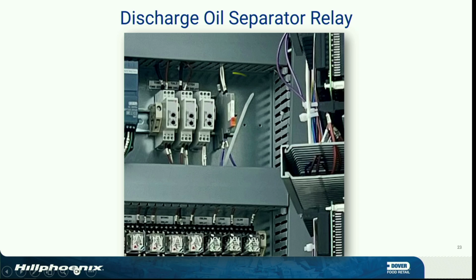What happens here? There we go. That's what we want. This is our solid state relay card. You can actually pull that orange tab down. The relay card will come out. You can order a new one, put it back in, because they will fail over time. I think they're good for a 50,000 pulse count. All right? 10 months. What's that? 10 months. Yeah. Hopefully not.